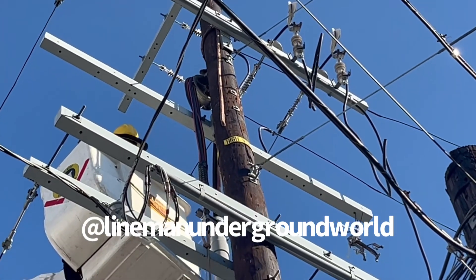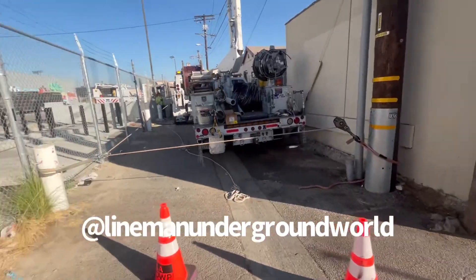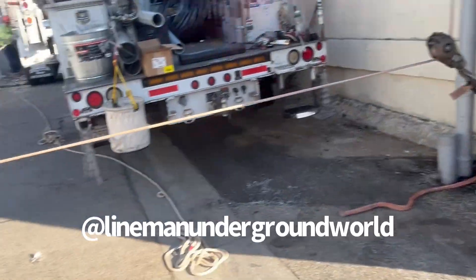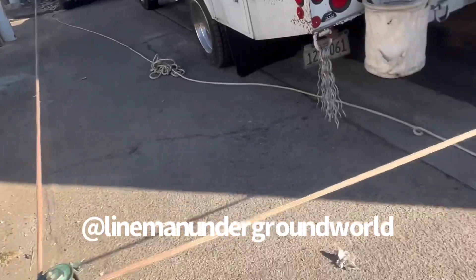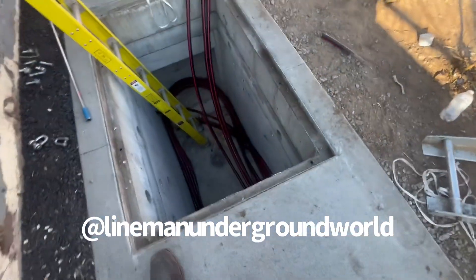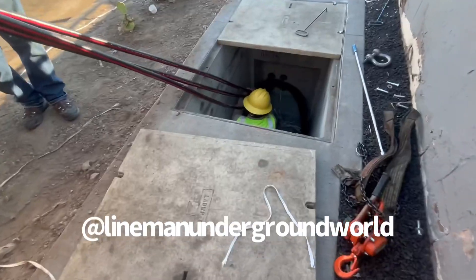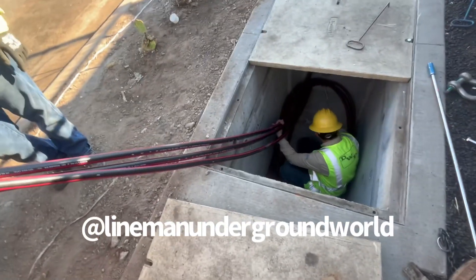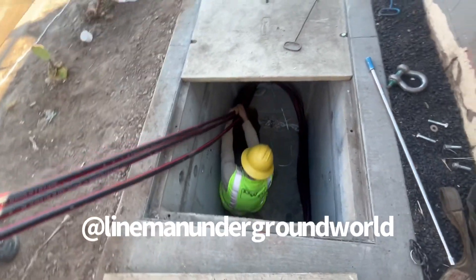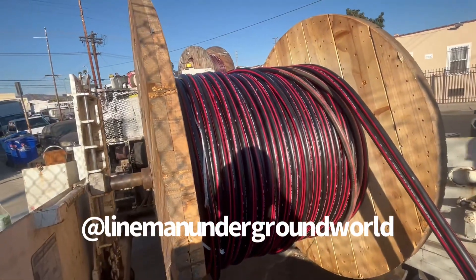She's tough right now, pulling hard. The kid's on the capstan over there - he's doing a fine job. He's got cable now - we're going three hundred feet, all off. We're going to pull back the cable to set the grip over there on the other side, then we'll cut it. But meantime we'll leave it the way it is right now.